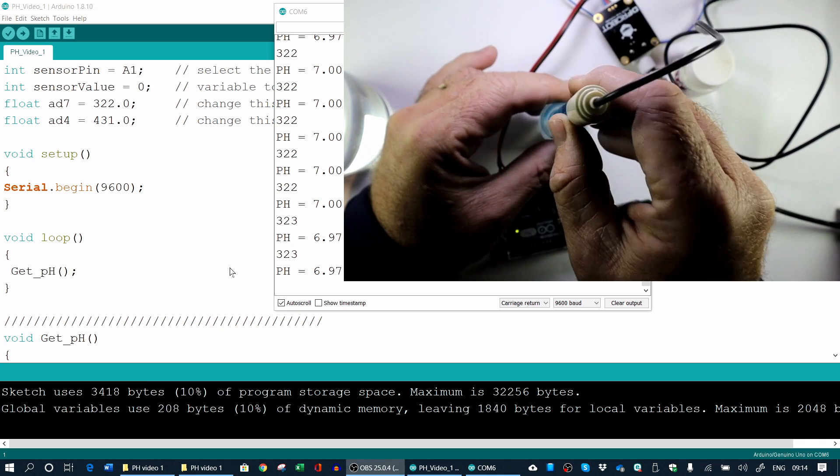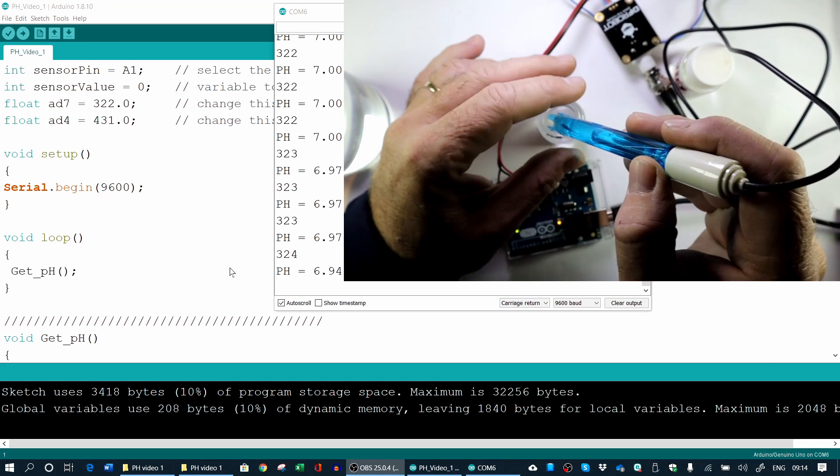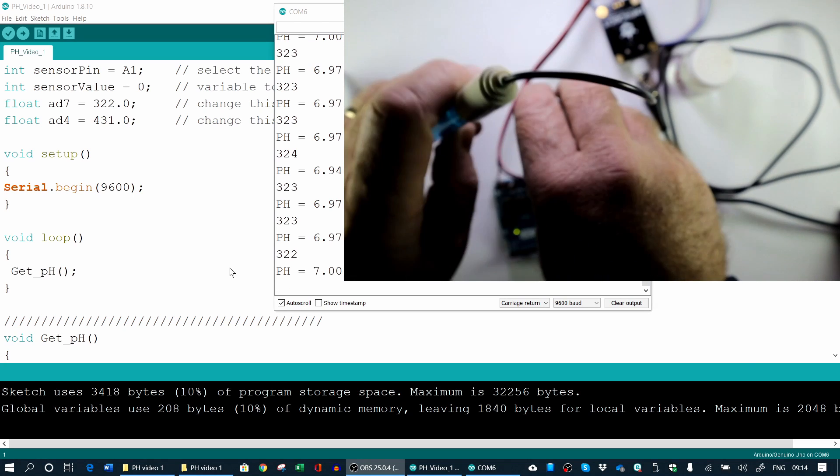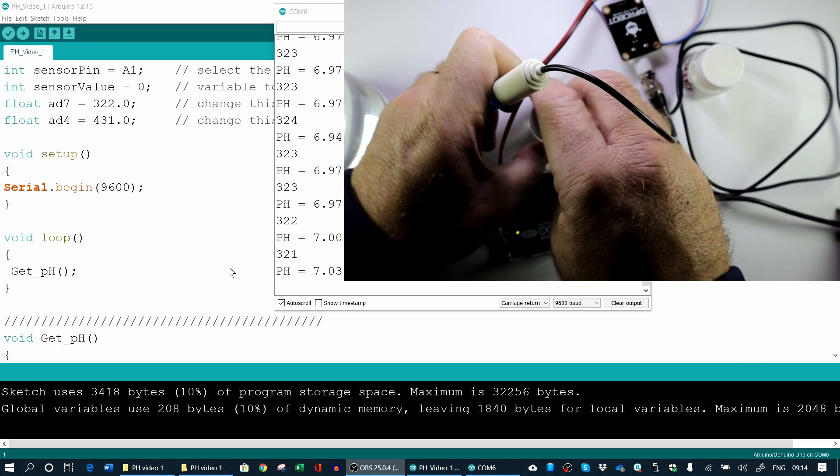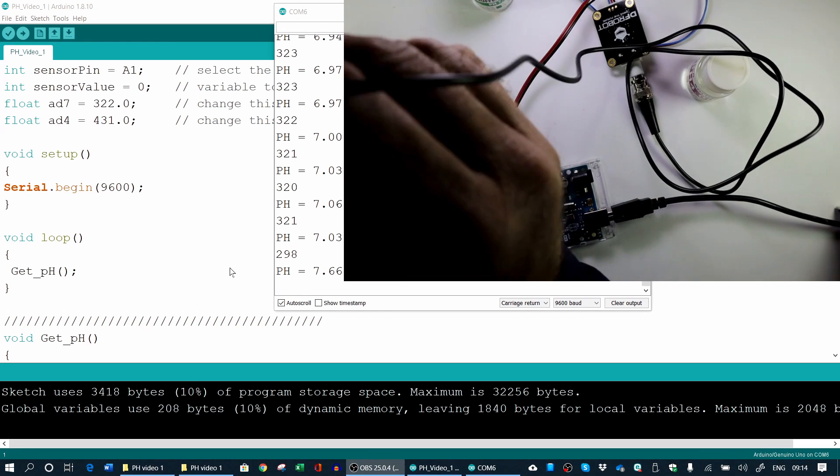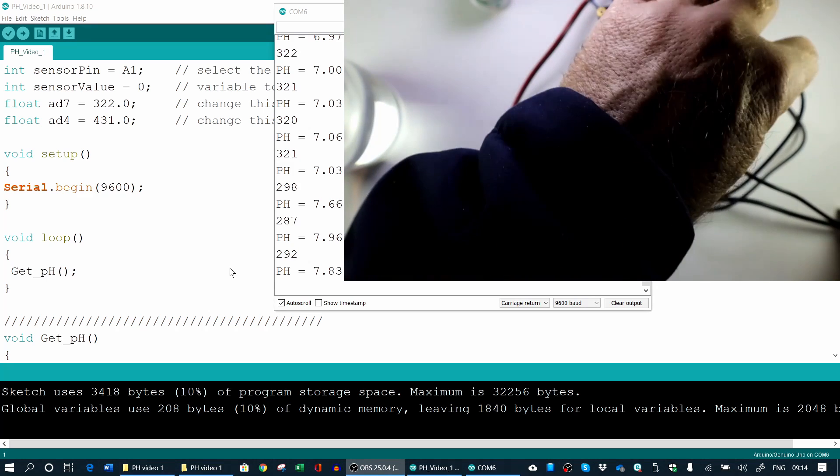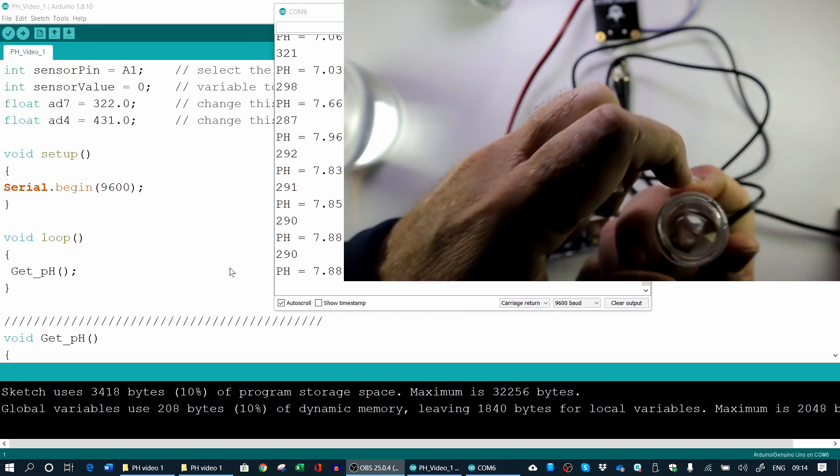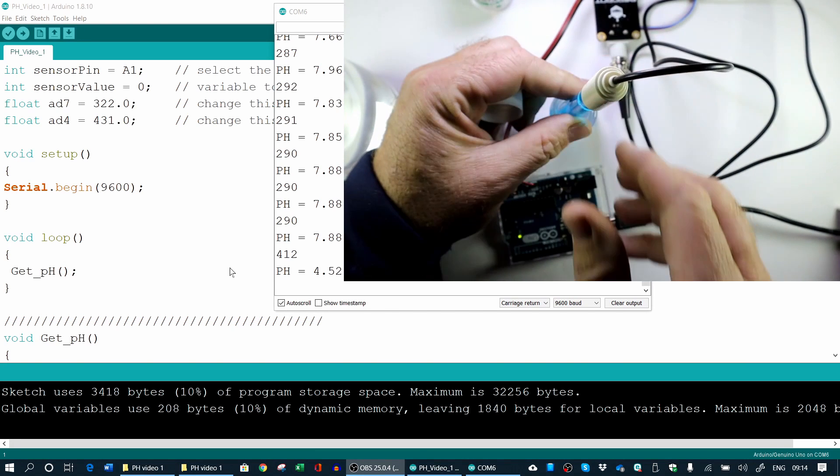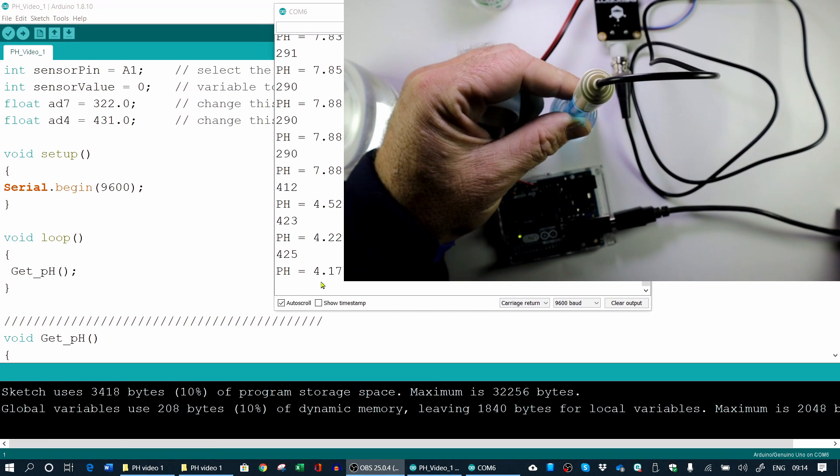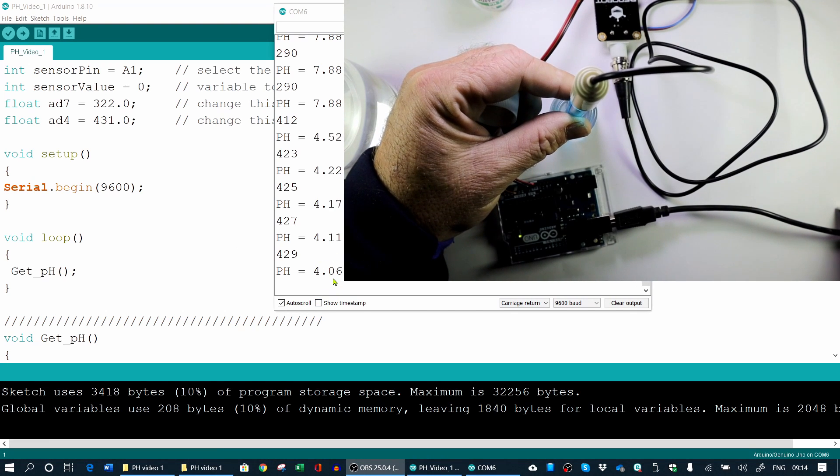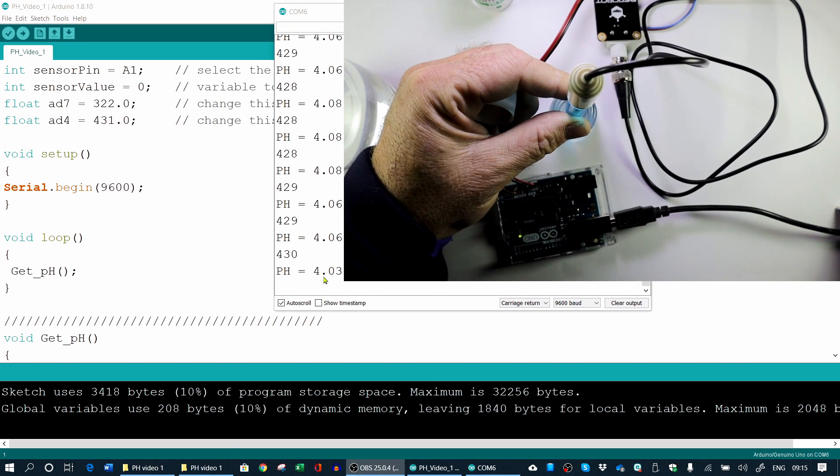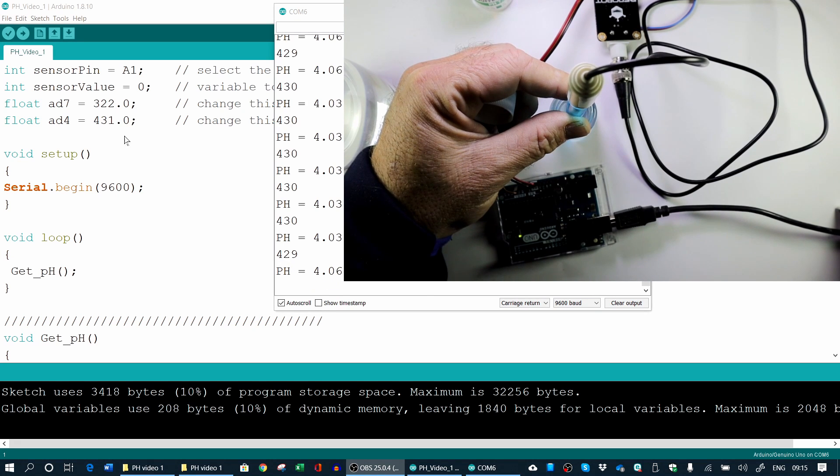So I'm now going to remove it from the seven buffer. And I'm going to just rinse it again. And now I'll take it to the four buffer. Let's put it in the four. And I'm just going to hold it like that. And let's see. So it's moving towards four here. You can see our values moving towards four. 4.03.